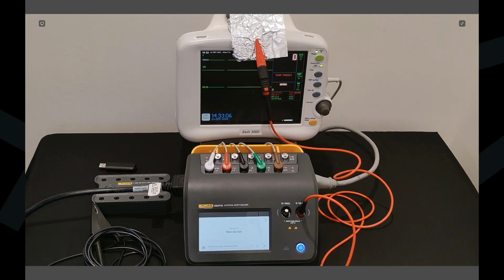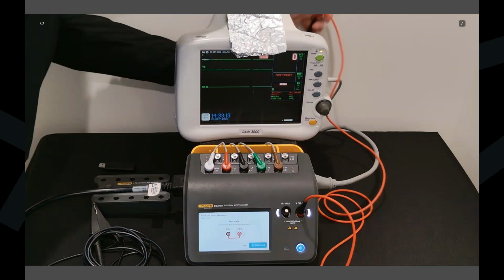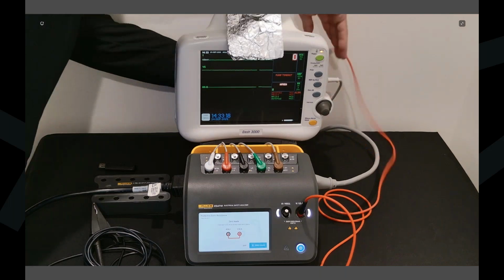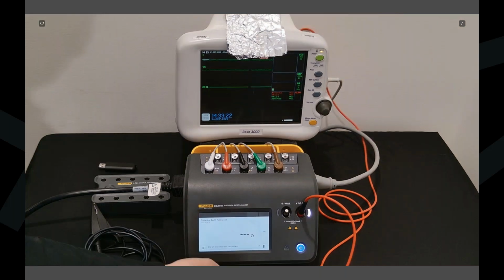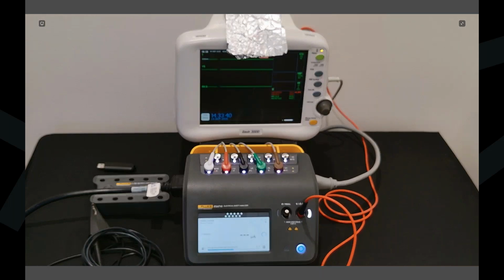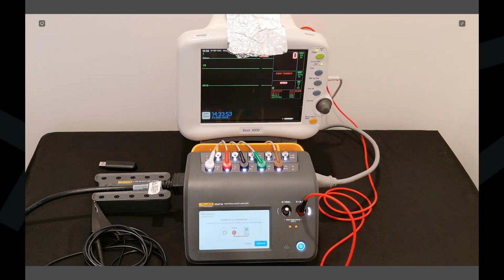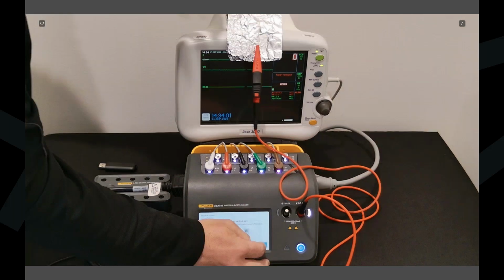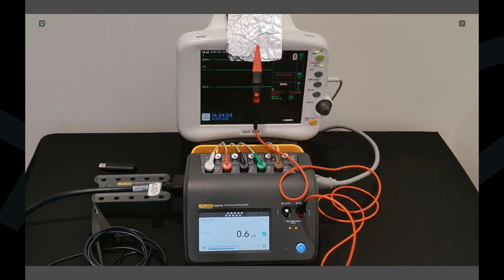So we've already zeroed our lead for the day. We'll go ahead and connect to our protected earth. Skip. Going through all your main voltage checks. Do a quick refocus. Now we want to connect to our non-applied part. Your leakage current, normal polarity. And again, you can set up this electrical safety test as complex as you want.